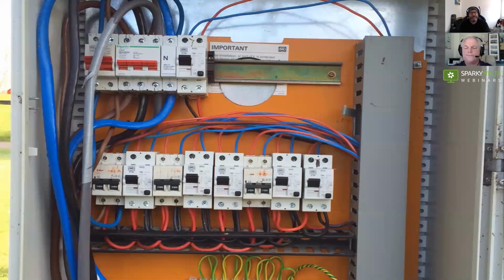This is, and there's no sense to that, is it? It's a bit like a Frankenstein. It's just a load of DIN rails have been put in, and they've made a panel. It's almost as if they thought, what have we got on the van? Well, we've got a number of RCDs, and we've got a number of double pole MCBs. So okay, that's just about enough to feed these 9 points, and we'll sort of swap them. We'll do one of these, and then one of those, and then one of these, and one of those. So you've got overcurrent protection on half of it. You've got RCD protection on half of it. Yeah, it's a complete mess.